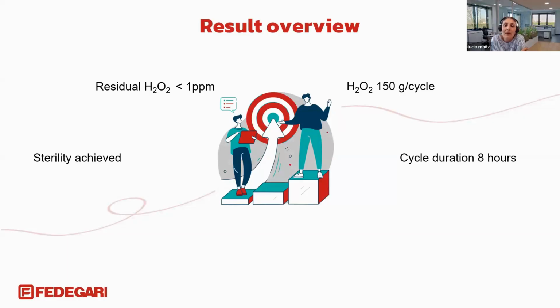So, to summarize the outcome of this case study, the sterility was achieved across all the tested configurations, confirming that the selected process parameters are suitable even for a complex geometry such as a long tubing set. And at the same time, the residual amount of H2O2 remains within acceptable limits, ensuring that safety-related requirements were met. The consumption is around 150 grams per cycle with a total cycle duration of around 8 hours.